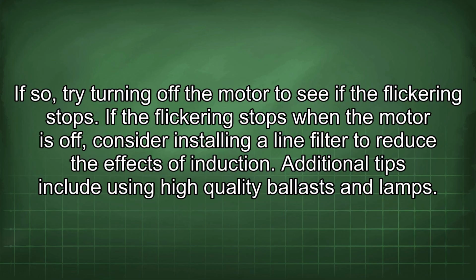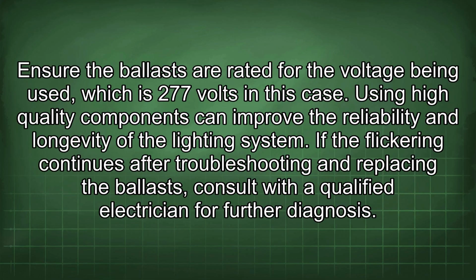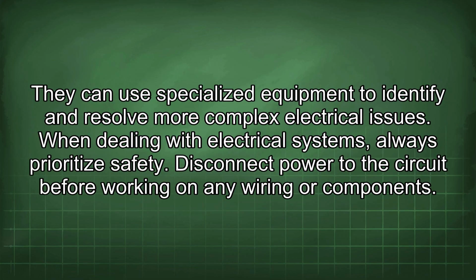Additional tips include using high-quality ballasts and lamps. Ensure the ballasts are rated for the voltage being used, which is 277 volts in this case. Using high-quality components can improve the reliability and longevity of the lighting system. If the flickering continues after troubleshooting and replacing the ballasts, consult with a qualified electrician for further diagnosis. They can use specialized equipment to identify and resolve more complex electrical issues.